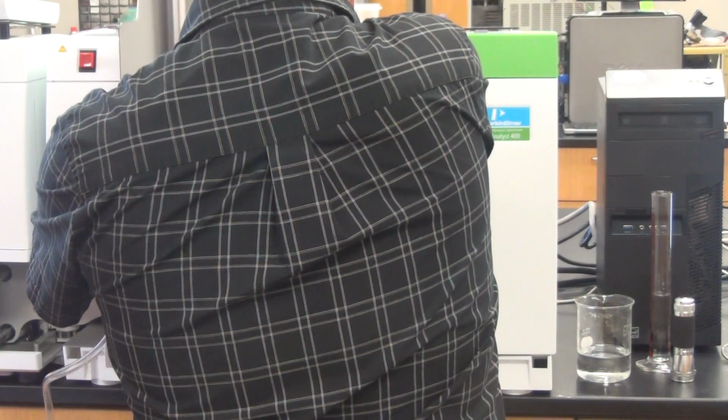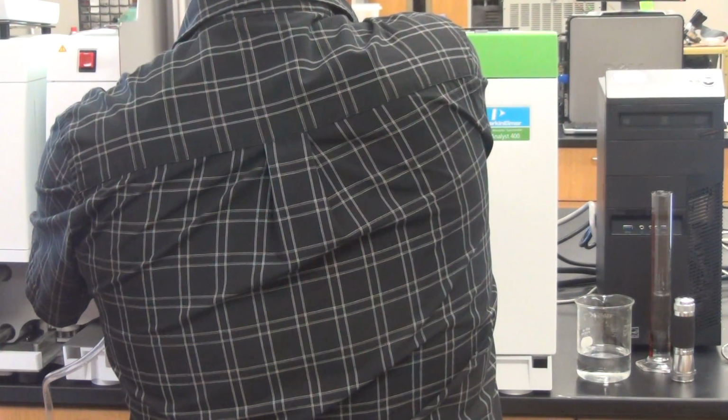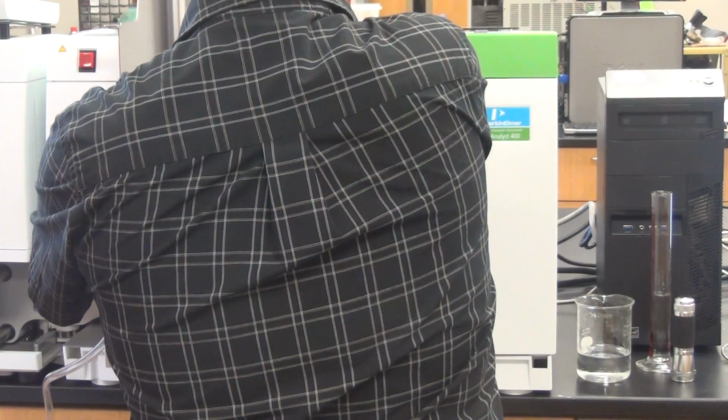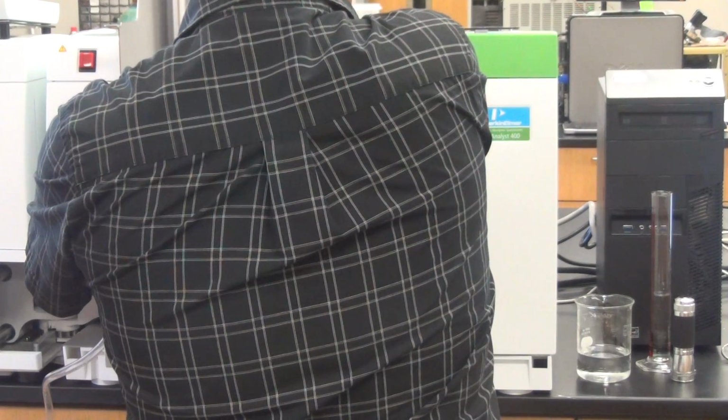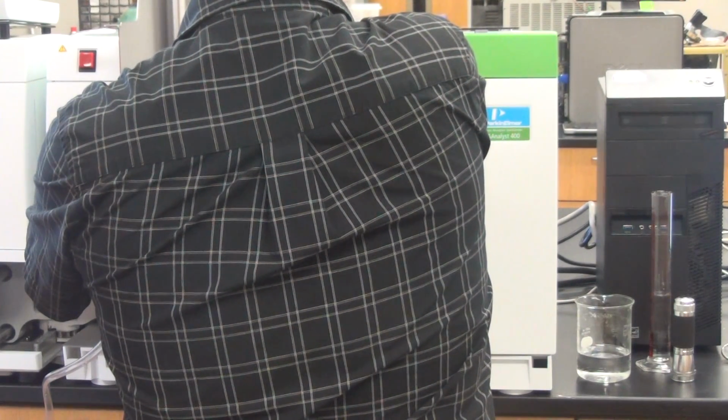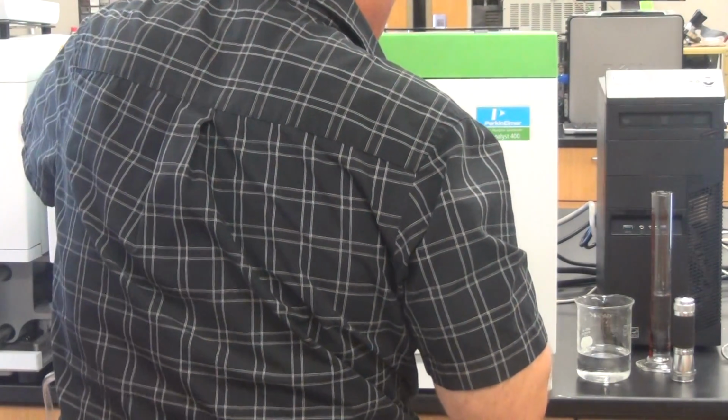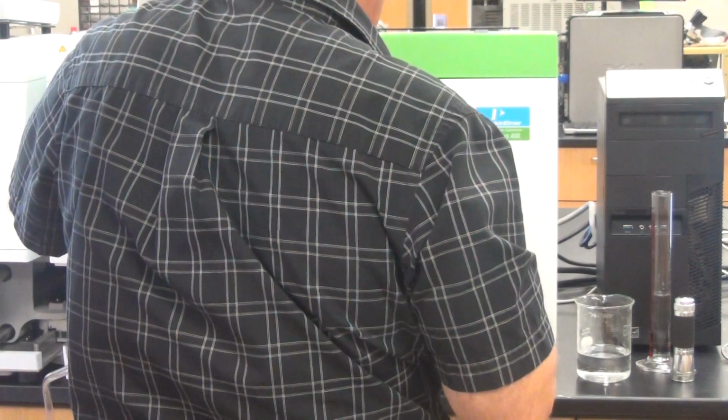So I'm looking at this, and there'll be a big area where it doesn't make any difference. But I'm going to set it in the middle of that area and then lock it down. Then how do you know if you really are in the middle? Well, actually, it went up when I tightened it, so we're not right in the middle of one of the adjustments.